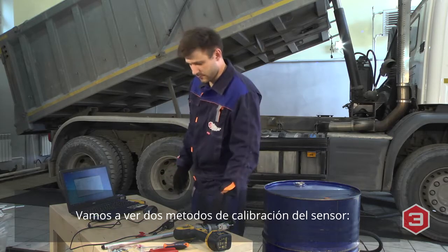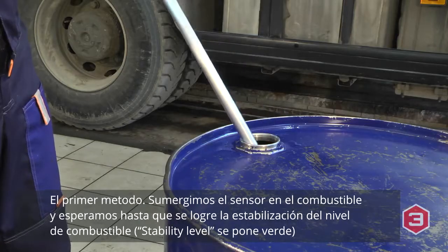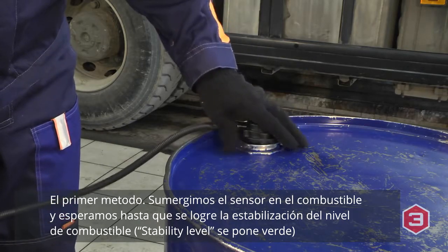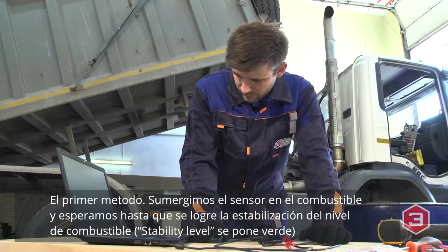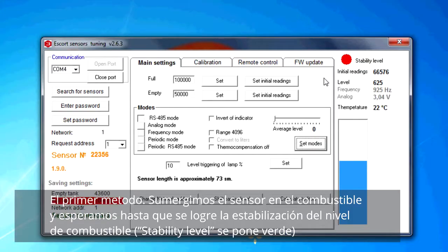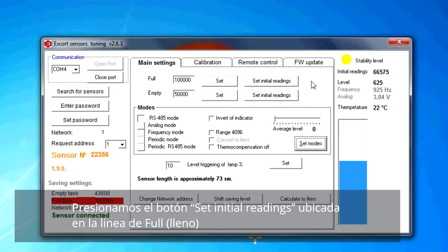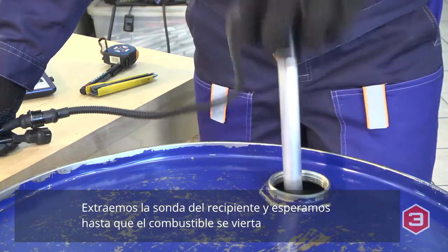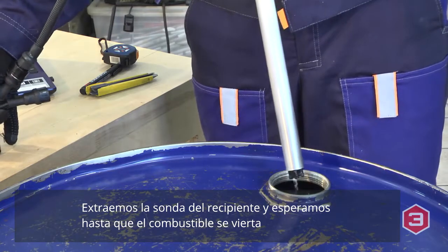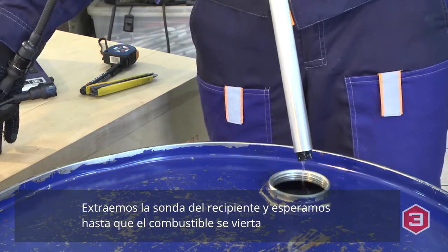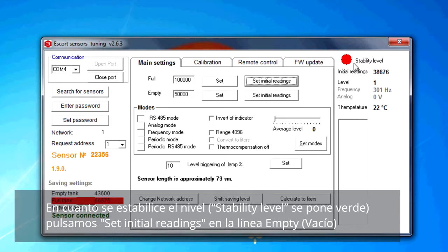There are two ways of sensor calibration available. The first way: immerse the sensor into the fuel and wait for the fuel level to stabilize. Press the Set Initial Readings button in front of the full caption. Take the sensor out of the tank and let the fuel drain. Wait for the fuel level to stabilize. Then click the Set Initial Readings button in front of the empty caption. Calibration is finished.